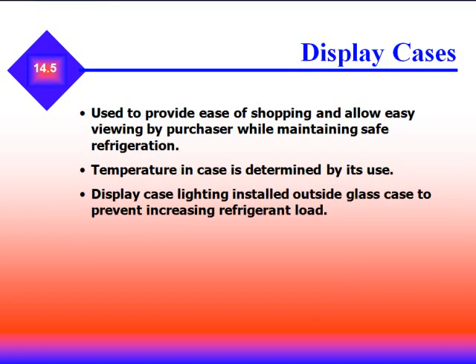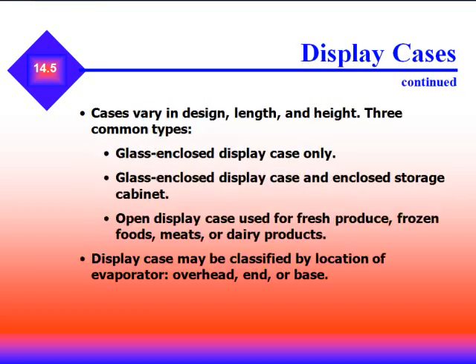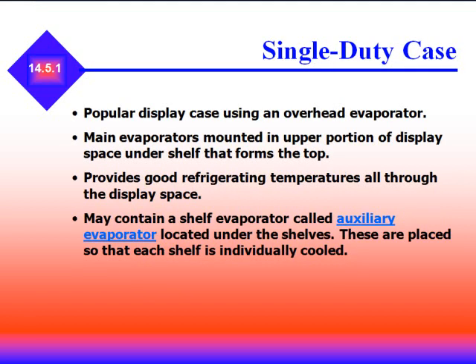Display cases are used to provide ease of shopping and allow viewing by the purchaser while maintaining safe refrigeration. The temperature in the case is determined by its use. Display case lighting is installed outside the glass case to prevent increased refrigerant load. Display cases come in varying design, length, and height — either glass-enclosed only or glass-enclosed with storage cabinet. Open display cases are used for fresh produce, frozen foods, meat, and dairy products. Display cases may be classified by the location of the evaporator: overhead, end, or base. The single-duty display case uses an overhead evaporator mounted in the upper portion of the display space, providing good refrigerating temperatures throughout. It may also contain a shelf evaporator, called an auxiliary evaporator, located under the shelves so each shelf is individually cooled.